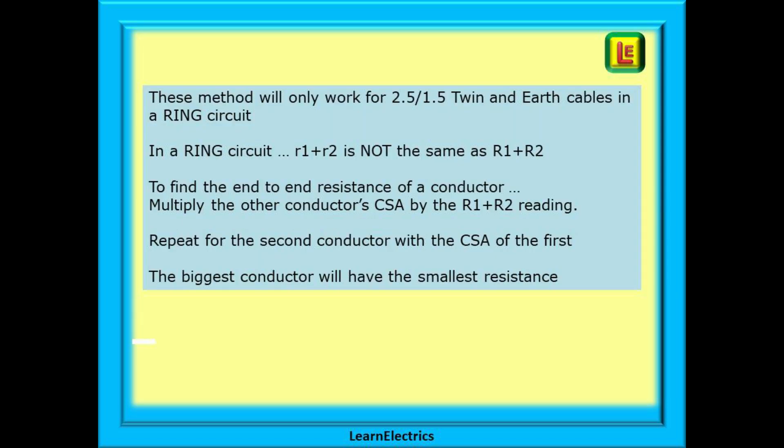In summary, this method will only work for 2.5 1.5 twin and earth cable in a ring circuit. In a ring circuit, little R1 plus little R2 is not the same as big R1 plus big R2. To find the end-to-end resistance of a conductor, multiply the other conductor's cross-sectional area by the big R1 plus R2 reading.